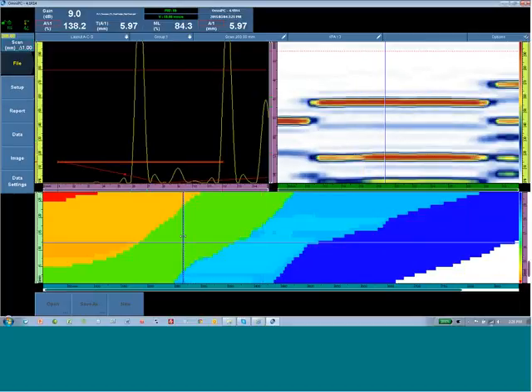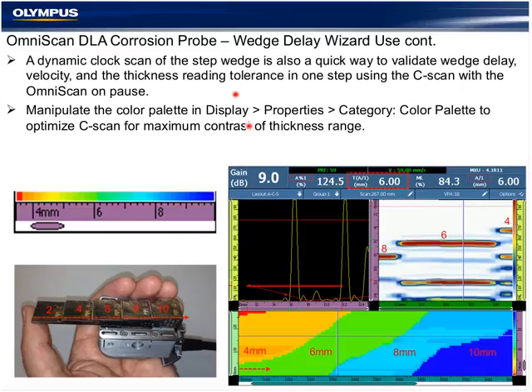And I can save this as a screenshot, or we can save the data file on the instrument for our inspection reports for before and after the inspections. And it's a very quick way of performing the wedge delay and velocity validation, similar to as we would with thickness readings from a UT gauge.